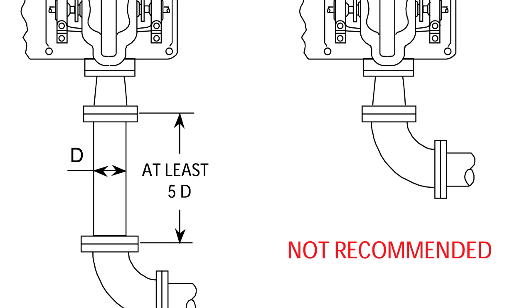Areas where we come into problems when we install pumps is when the area is too tight and we have to put in a pump with an elbow that's close to the eye of the impeller. This can cause problems because if we have an elbow coming in very close to the suction, we're going to have large-scale turbulence and the pump won't behave as well as it would otherwise.